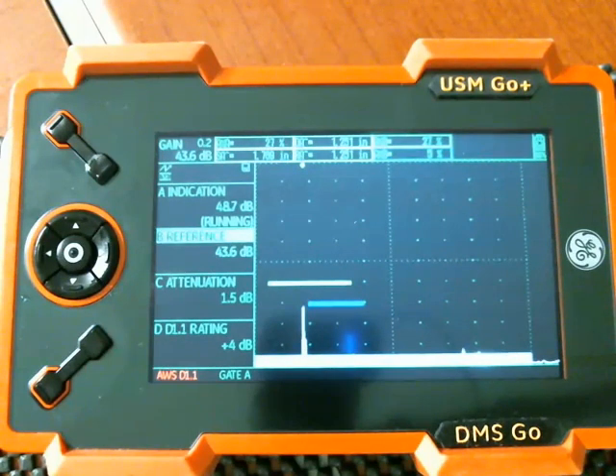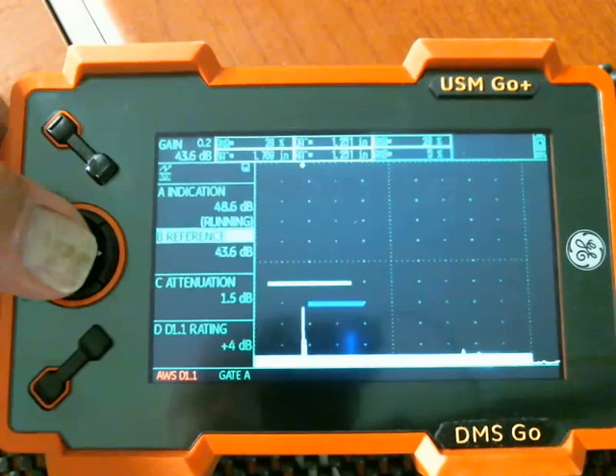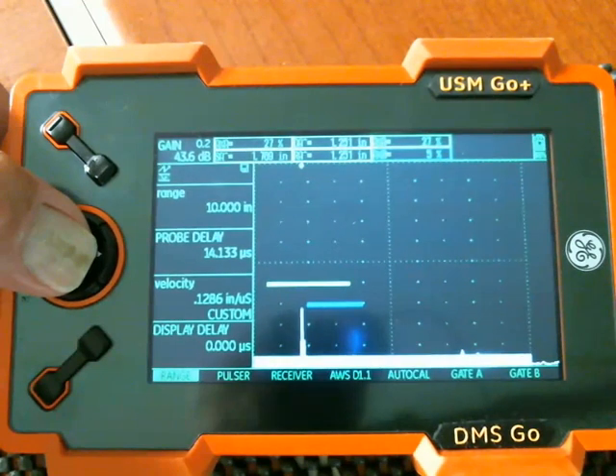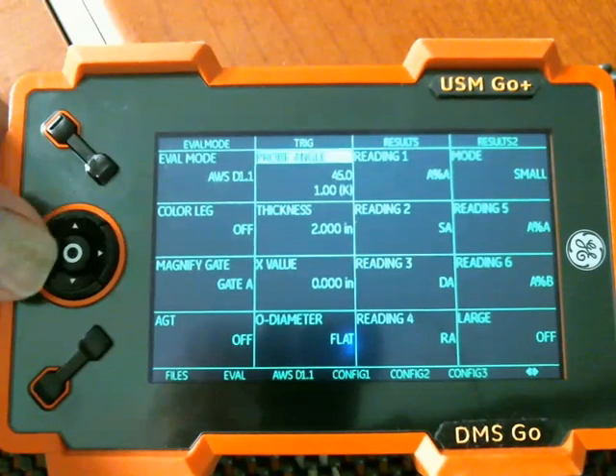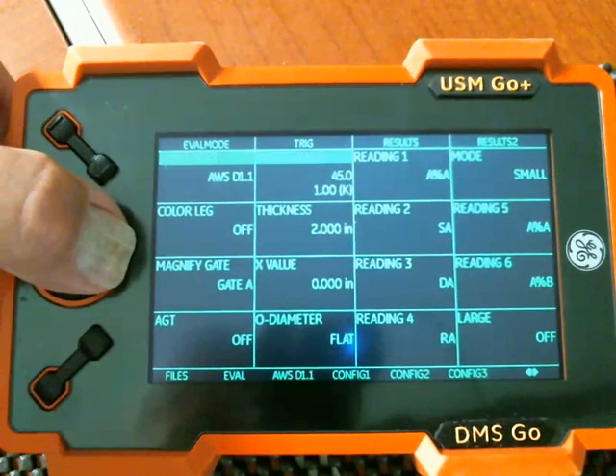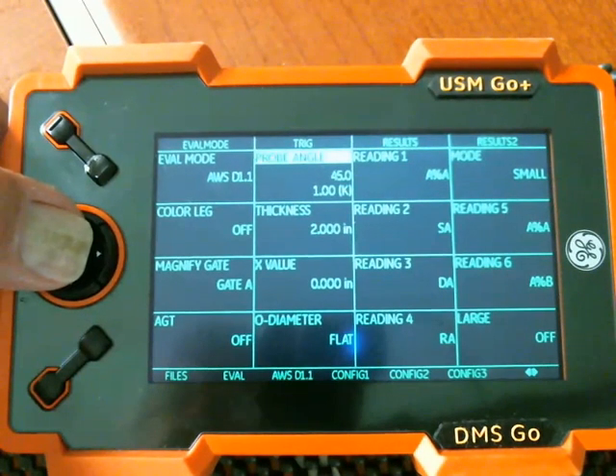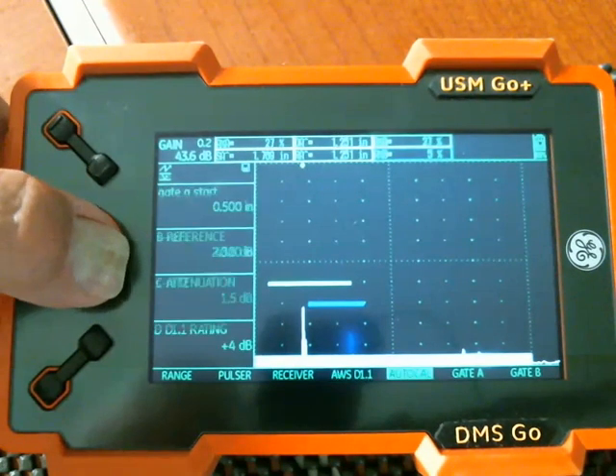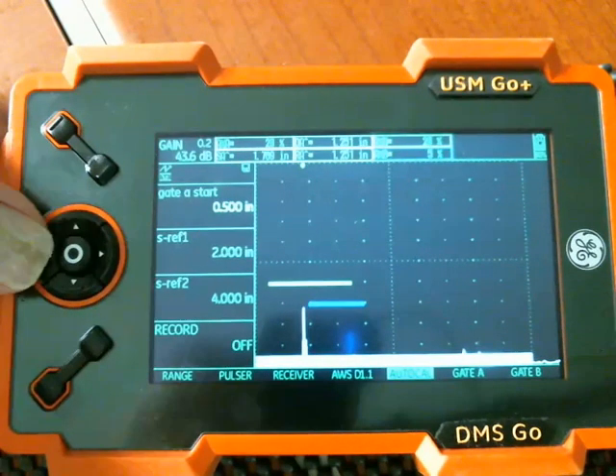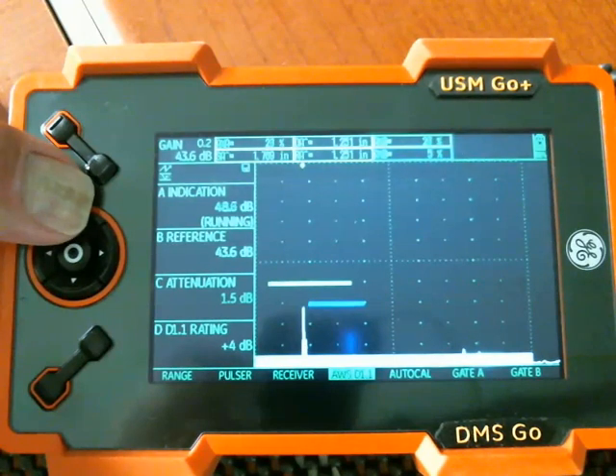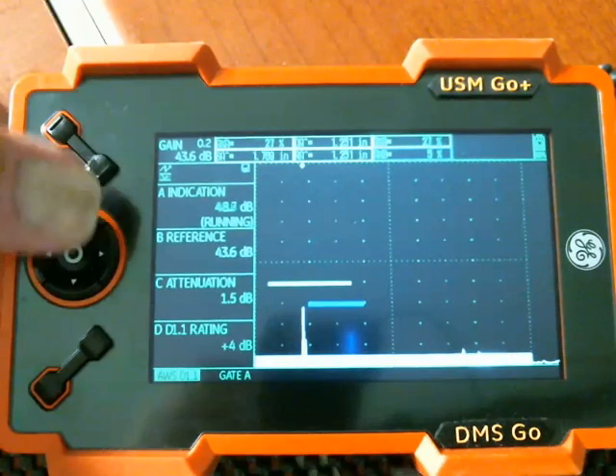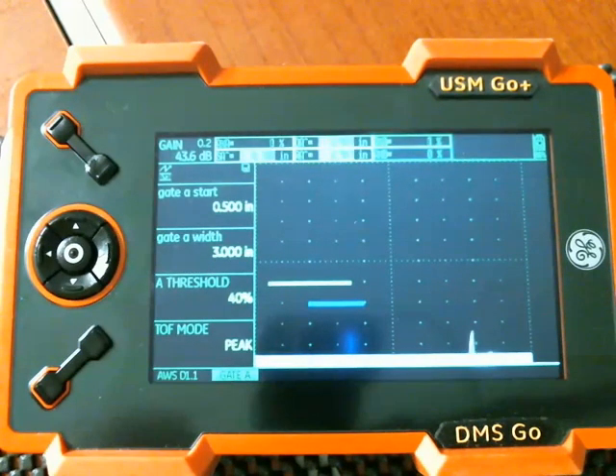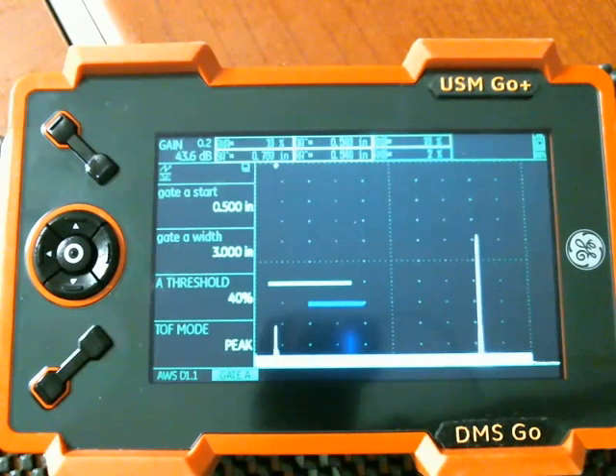So again, that's the basic setup to get the AWS D1.1 evaluation method working. So just to recap, we'll go home here. The most important thing is in the back menus. In the eval menu, I need to select AWS D1.1 as my evaluation mode. And I need to set up my probe angle. Given those two things, I came back out. I used the AutoCal to set up the delay and velocity for that probe. I went to the AWS setup menu. Went up one click. That gives me the AWS menu and a gate menu.